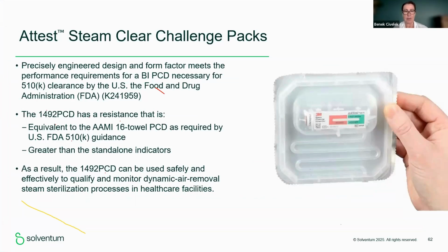In general, as a summary, we can say that both designs, the clear challenge packs for both steam and hydrogen peroxide, are designed in a precise engineered way. And here in steam, we have the equivalence with the 16 towel pack PCD, and also a greater resistance than the standalone indicators. It is recommended to be used safely and effectively, both in routine monitoring and also in qualification testing of steam sterilizers.